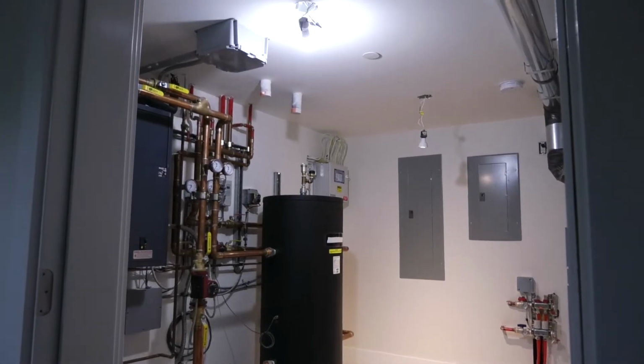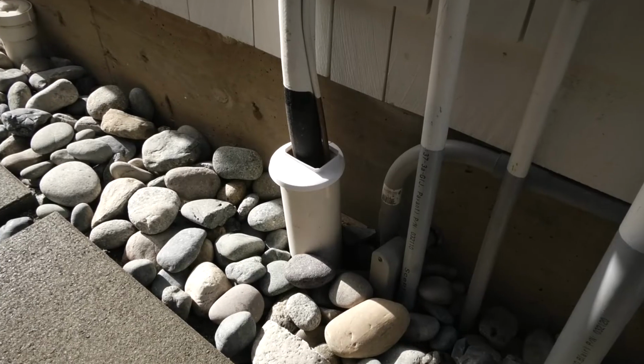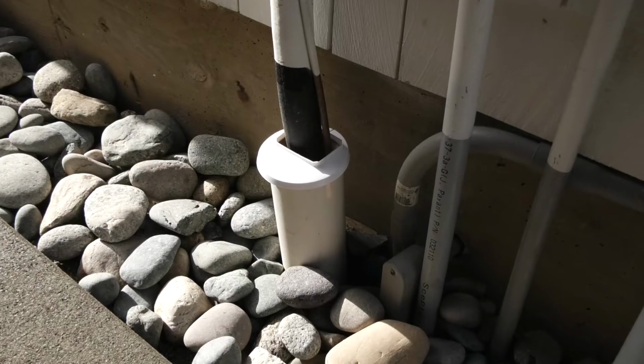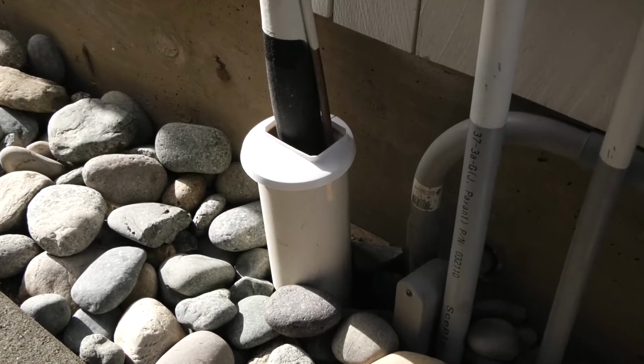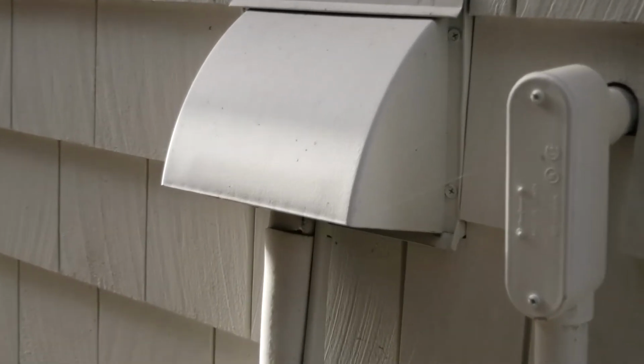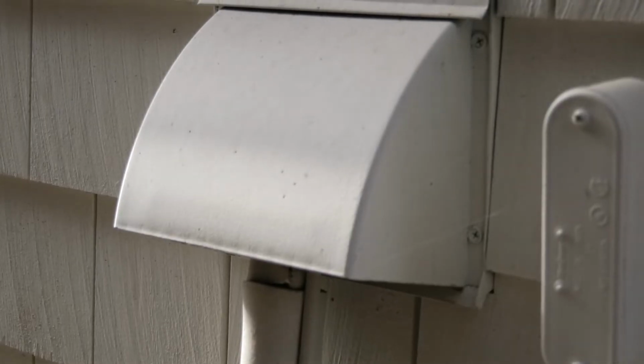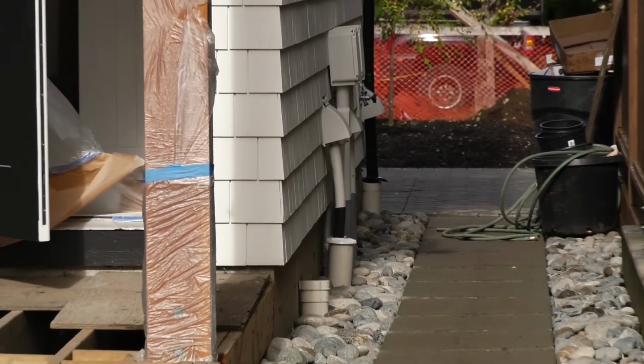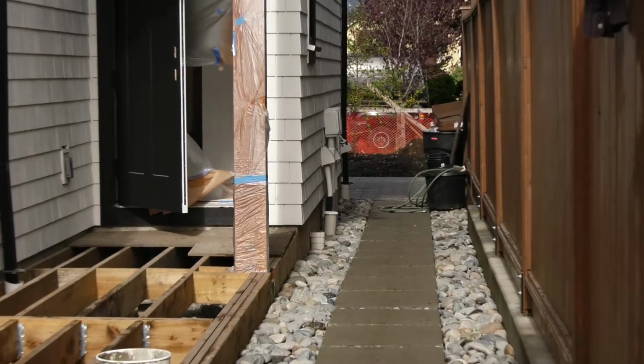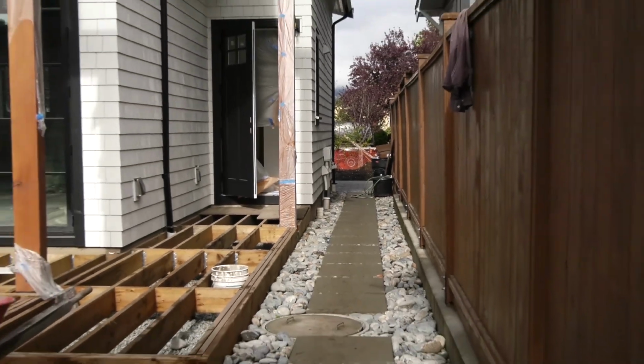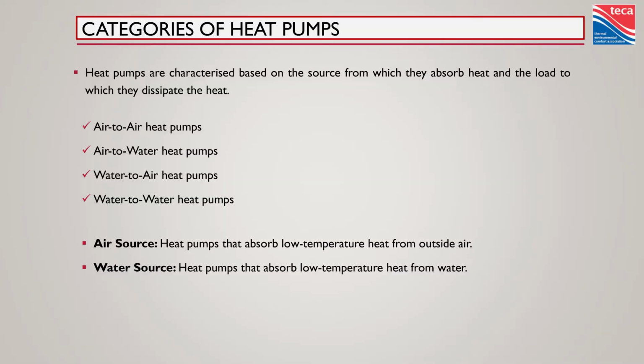So we have air-to-air heat pumps, probably the most prevalent we're familiar with. Air source heat pump outside using forced air heat delivery inside. Air to water, the only difference is hydronic heat delivery inside, still air source heat pump. Then we have water to air, not to be confused with air to water. Water to air is a water source heat pump using forced air. And then water to water is a water source heat pump using hydronics to distribute that heat energy.